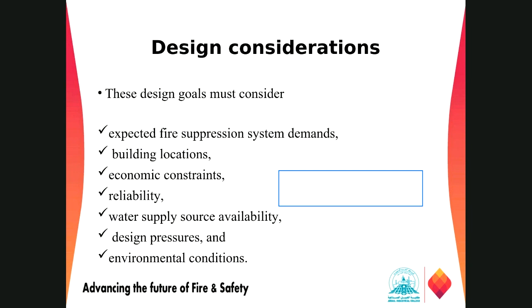We have to make sure regarding the maximum working pressure of a fire protection equipment. And when selecting the type and class of pipe to be used, maybe 175 is the most common in the water-based fire protection system, except the standpipe system. A standpipe system sometimes works up to 24 bar or maybe higher because of the height of the building. These are special cases that we have to consider. But in most cases for underground networks, we need 150 psi, and for the above ground sprinkler system piping, 175 is more than enough for our design basis.